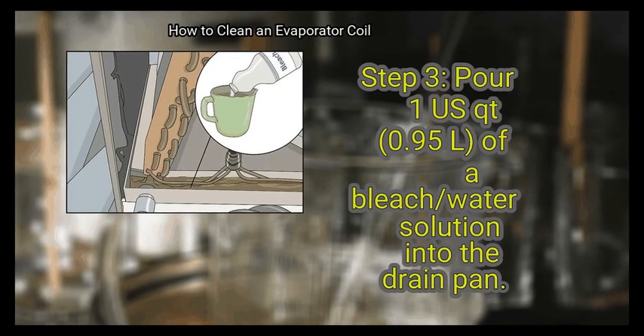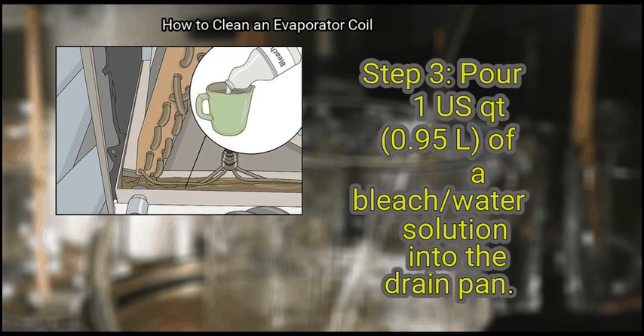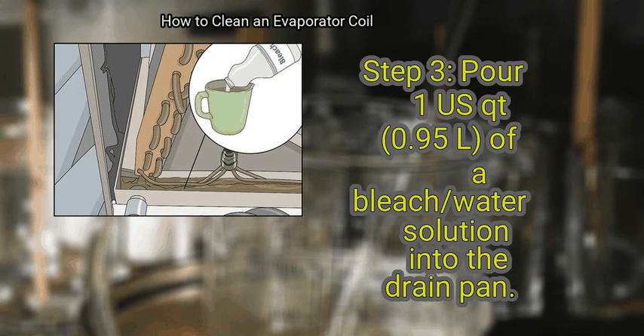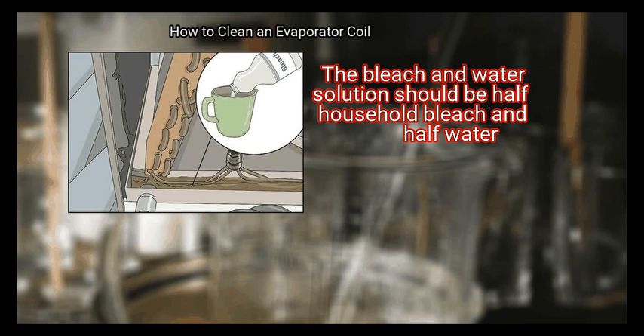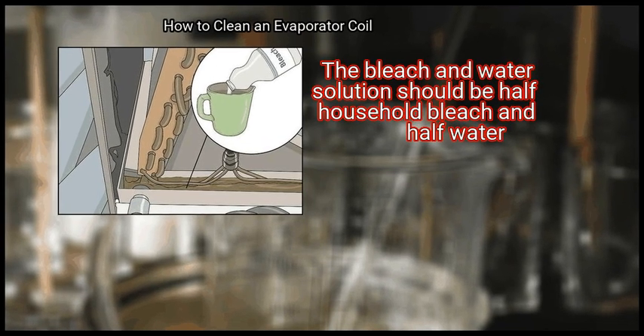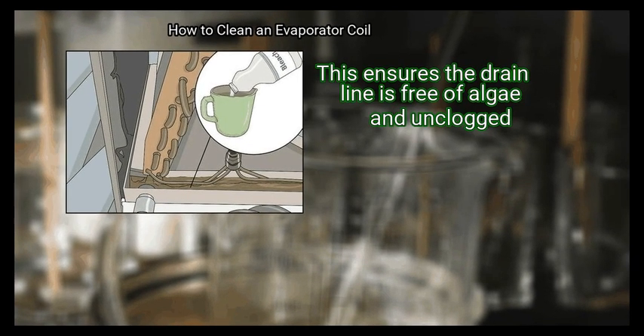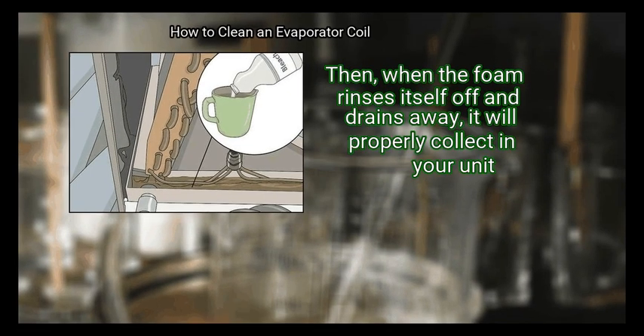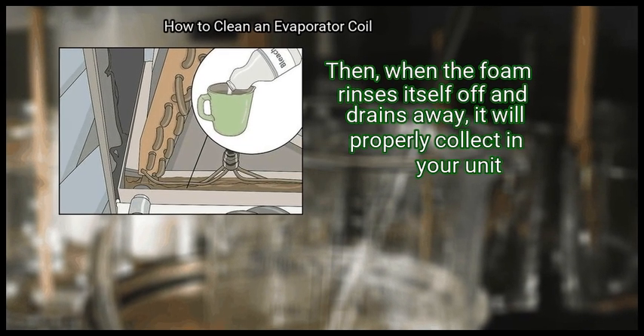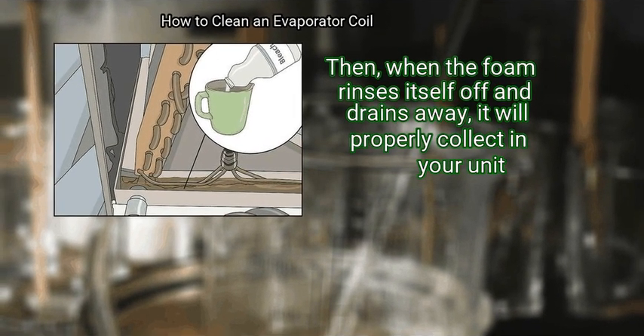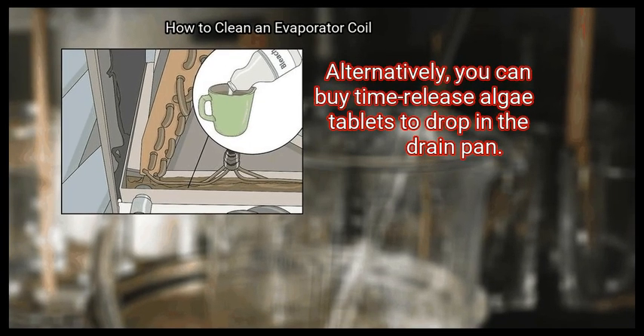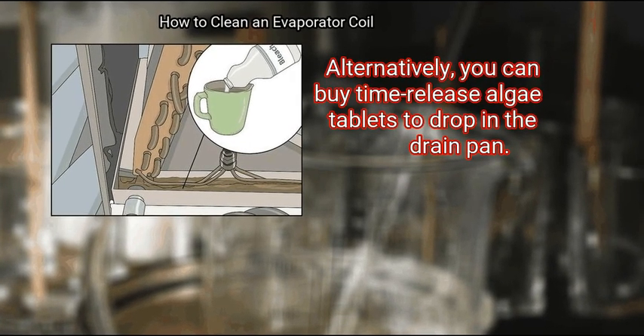Step 3. Pour 1 US qt, 0.95 L, of a bleach and water solution into the drain pan. The bleach and water solution should be half household bleach and half water. This ensures the drain line is free of algae and unclogged. Then, when the foam rinses itself off and drains away, it will properly collect in your unit. Alternatively, you can buy time-release algae tablets to drop in the drain pan.